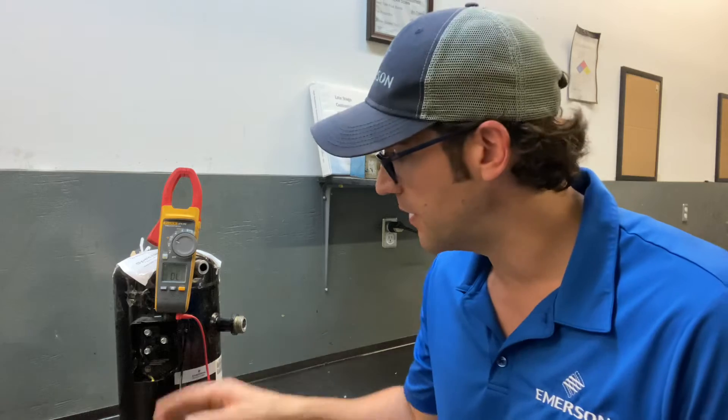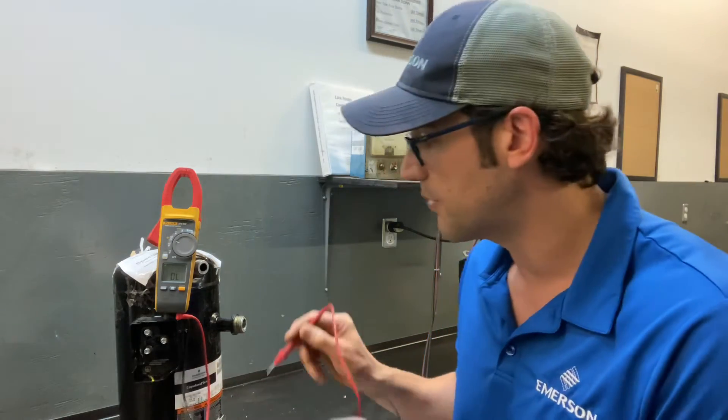You should always be checking from the terminals, because if you check from the contactor — and I've done this many times before from the load side or the compressor side — you could get weird readings. But that could be the contactor that's the issue, it could be the wires down to the compressor, it could be the connectors of the wires, or it could be this terminal block right here on the compressor that failed.